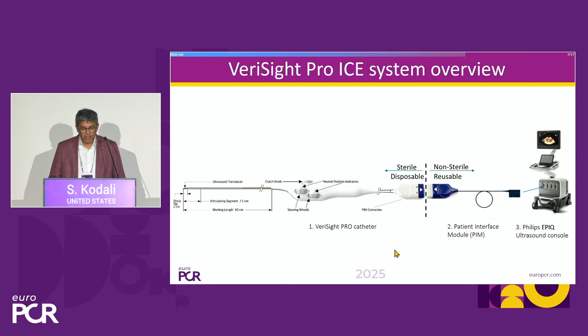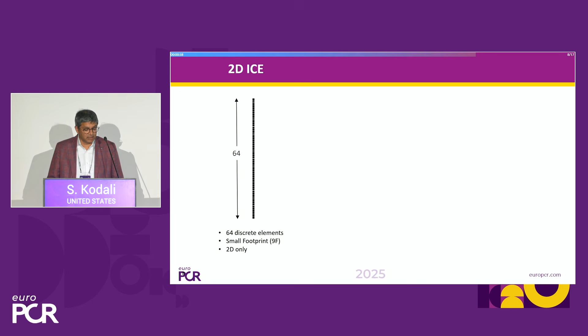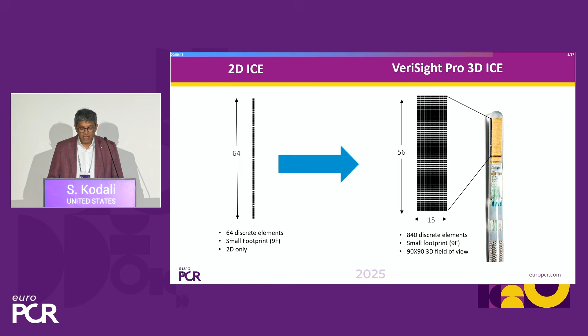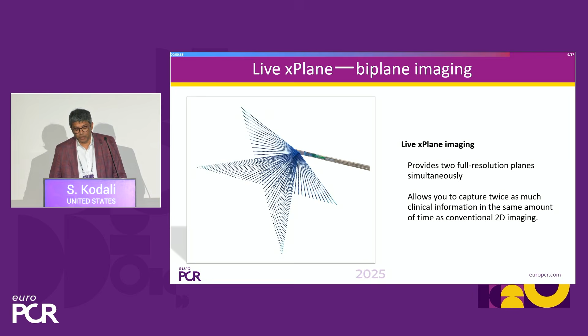Just to understand how it differs from 2D ICE: 2D ICE is 64 discrete elements. It's 9 French, but 2D only. With the VeriSight 3D ICE probe, you see here it's 840 discrete elements, phased array. It's still 9 French, and it has a 90 by 90 3D field of view. It provides the ability to do X-plane imaging like we have with our 3D probes, and you get 2 full resolution planes simultaneously.